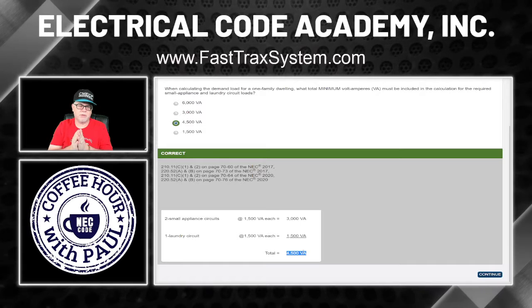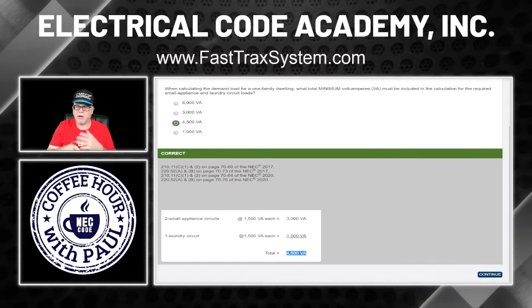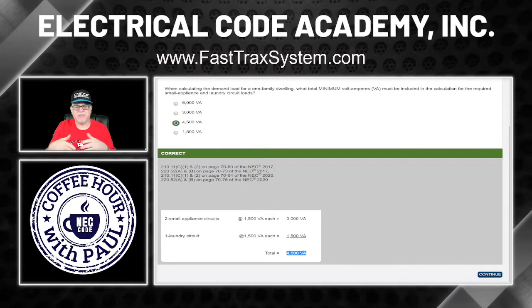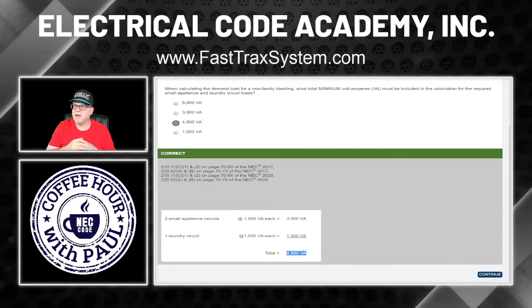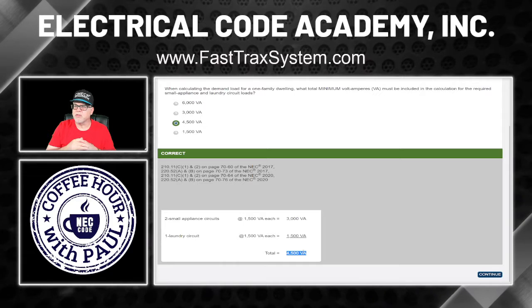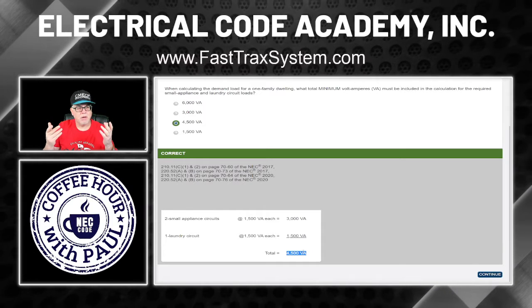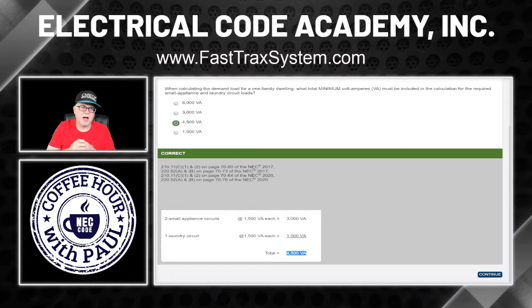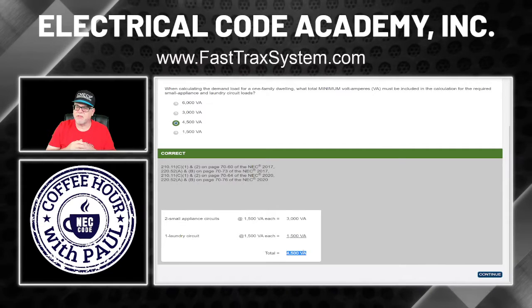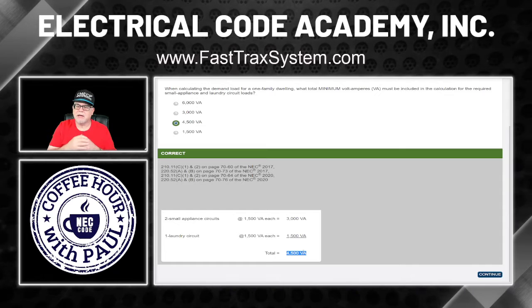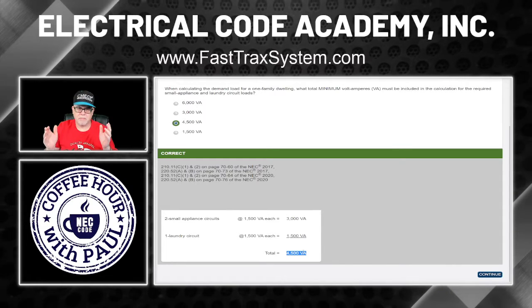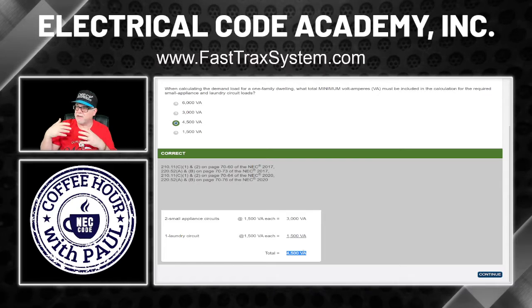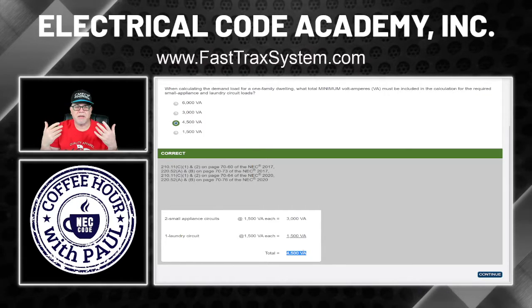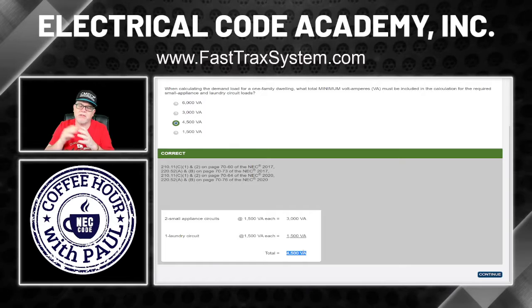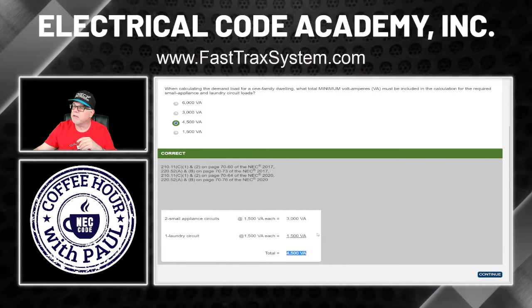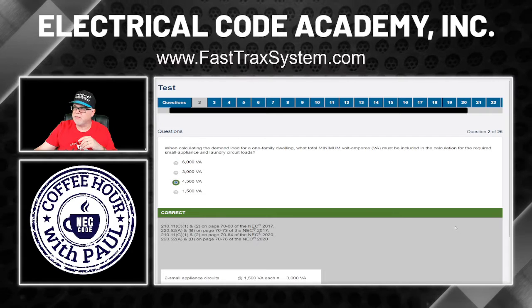All that question did, folks, was ask me, what is the demand load that I have to contribute for the small appliance and the laundry loads? Well, we don't have enough information to do anything other than pull the VA value directly from the NEC. And that's it. There's nothing we can apply. We can't apply any real demands. We can't do any of that because we don't have all the variables. All we're doing is answering the question, and that's all you need to do for that. Okay, so that answer there is 4,500. Okay?